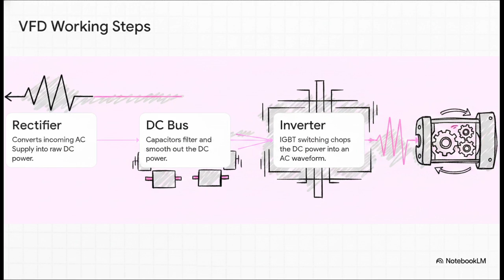All right, let's look under the hood in Section 3, how a VFD works. It's essentially a 4-step journey, taking power from AC to DC and back again. Step 1, your standard AC supply enters the rectifier, which converts it into raw DC power. Step 2, the DC bus and capacitor step in. Think of them like a giant sponge. They filter and smooth out all those messy electrical ripples. Step 3 is the inverter. This is where highly advanced switches, called IGBTs, rapidly chop that smooth DC power back into a brand new AC waveform. And finally, step 4, this newly synthesized variable power is sent directly to the motor.